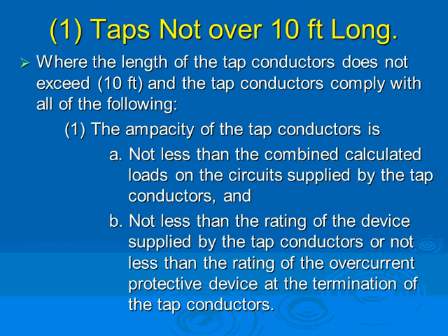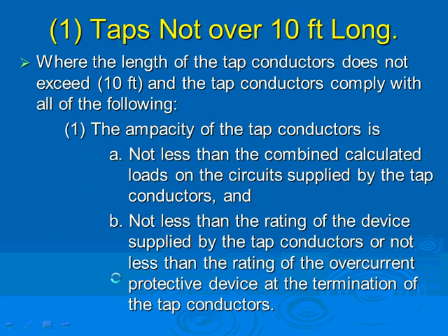There's a couple of tap rules, guys, dear to my heart, and I'm sure dear to yours. Tap rule number 1 is really cool. And remember, Chad thinks everything is cool. So here's tap rule number 1, and I'm going to summarize it this way. Suppose I have a 300 amp feeder, okay? And for a 300 amp feeder, I'm just going to size that. What would that give me? 300 kcmil, I think. Can anybody size that one for me?